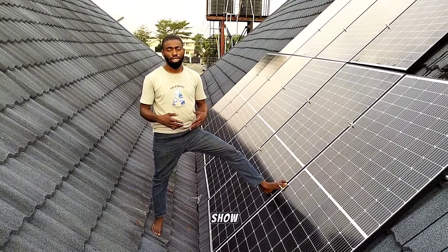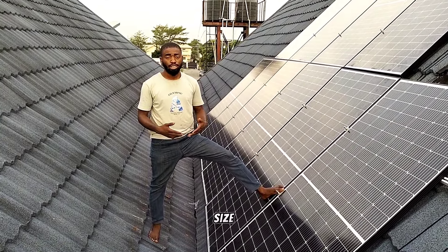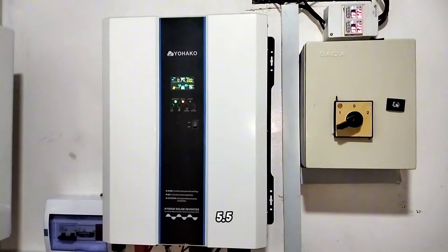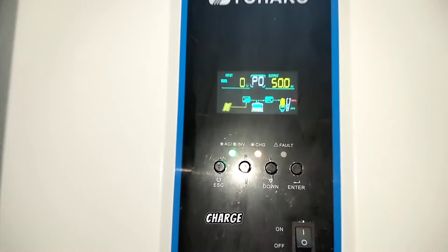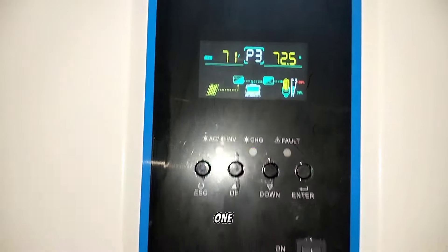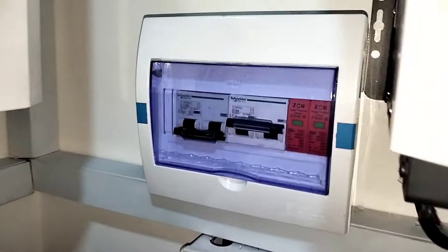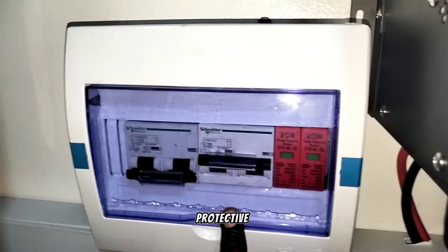I'll take you guys down to show you the amount of load this place is consuming, and show you the battery and the size of the inverter we used. Down here we have 2 units of 5.5 kVA inverters, Yohako brand. Each of them comes with a built-in charge controller of 100 amps. You can see this one is carrying about 55% load, and the whole panel is connected to this one because I didn't connect the other one. We are generating about 72.6 amps coming from the solar panels. Then down here we have 2 breakers — one will serve one inverter, the other will serve the second inverter — and the SPD, which is the surge protective device.